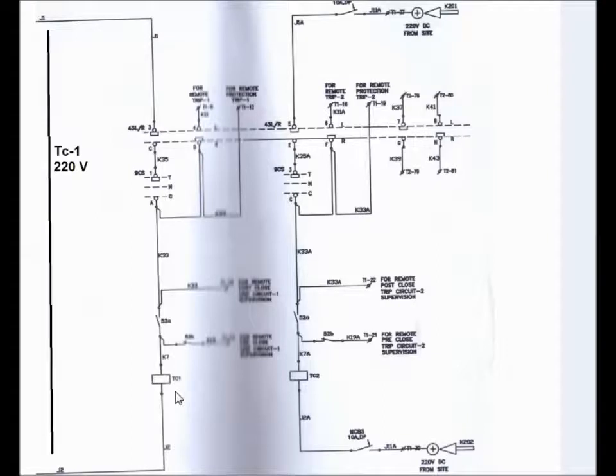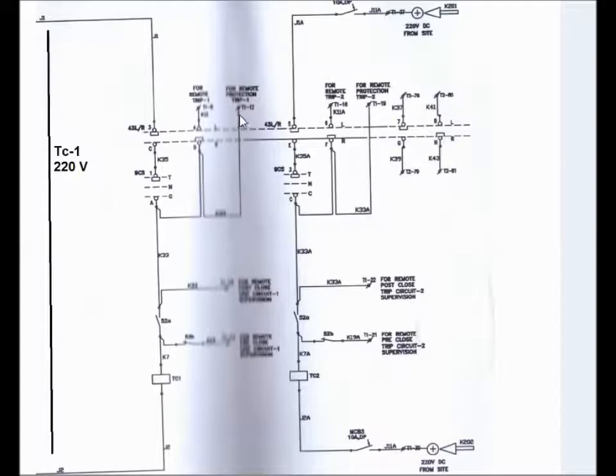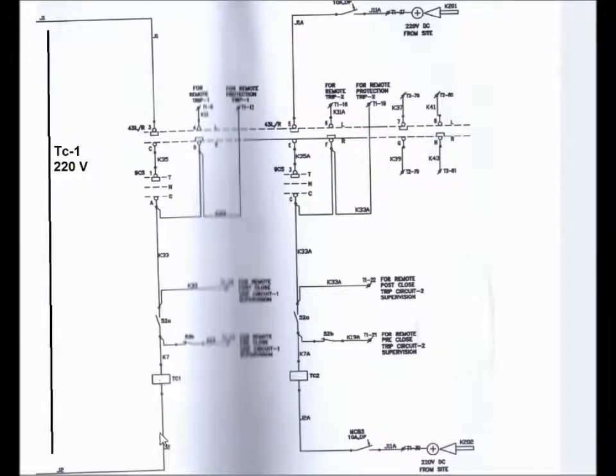As soon as the trip coil energizes, the breaker will be in OFF condition. For remote tripping, the local-remote selector switch must be in remote position. For protection tripping, if relay 86, the master trip relay, operates during a fault condition, the DC positive comes from the control and relay panel via the 86 master trip relay contact, through the auxiliary contact of the circuit breaker, to TC1.